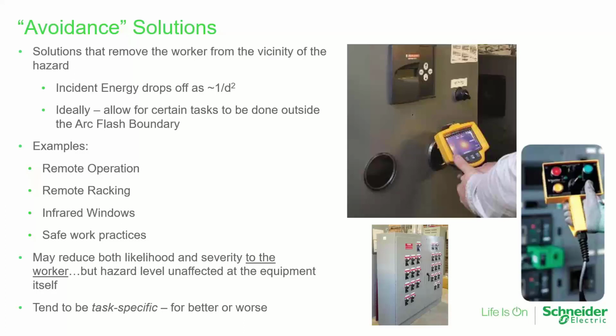Ideally, we find solutions that allow for tasks to be done outside the arc flash boundary. And that picture that I have on the top here, where we've got a guy doing a thermographic scan through an infrared window, is a good example of this. Traditionally, to do the infrared scans, you're pulling covers off of energized equipment, exposed to the live bus inside the gear. Well, if all you have to do is flip up a little cover on a window, you don't remove the cover, you don't open up the gear, you're not exposed anymore. You're by definition outside the arc flash boundary in that case. And so there are many examples of solutions that fall into this category: remote operation, remote racking of circuit breakers.